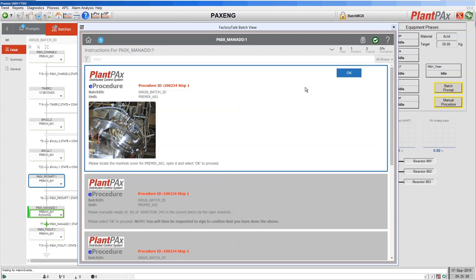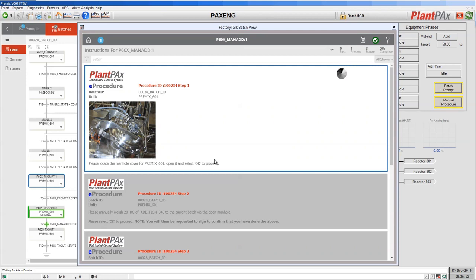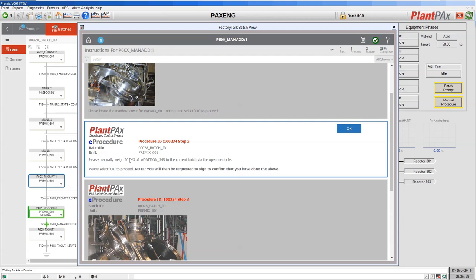Let's follow this manual procedure. In the first step, it's asking us to go and find the right manhole, open it, confirm that we've opened it, and then click yes. In the second step, we're now being asked to add material. The amount of material to add and the lot number of the material has come from the recipe — so these are not defined in the web page. These values are dynamic. The same for the batch ID — this is a dynamic value that will change every time the recipe runs.